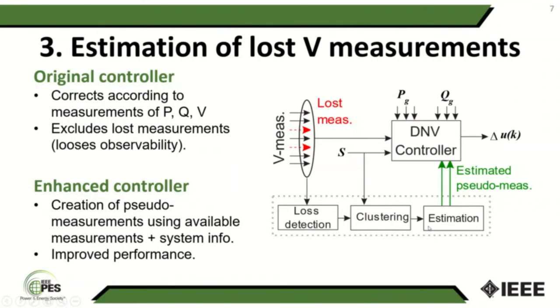Now that we defined the control scheme, we can speak about the additional blocks for estimation of lost voltage measurements. The original controller uses P, Q, and V measurements to predict the optimal control actions. However, in case of lost voltage measurements, it excludes such bus from the control buses list. The enhanced version of the controller creates pseudo measurements based on the available measurements and the characteristics of the grid. This allows for improved performance.